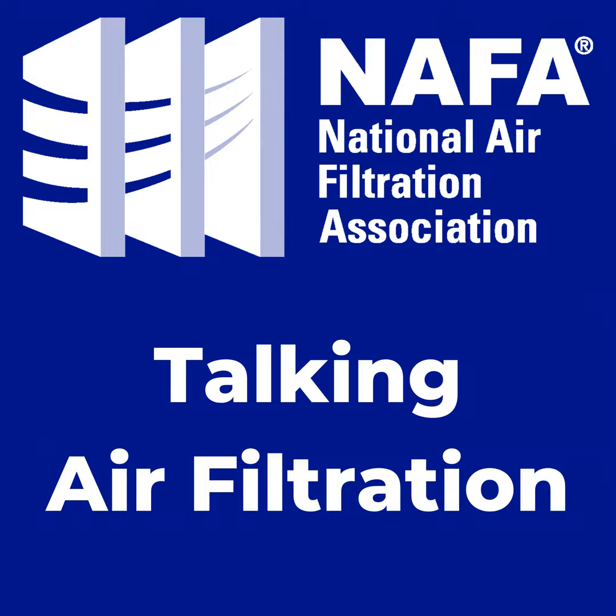ISO 16890 normalizes the filter efficiency to an urban particle size distribution. And I know there's some issues with that mechanism and why they do that. But the point is, when you look at the particles that are in the air, you have an ultra-fine particle range and you have a larger particle size range. That's just how outdoor air is made up. So when you look at what dust we're testing the filters with, it's all large particles. We don't have a lot of the ultra-fine particles in the test dust.